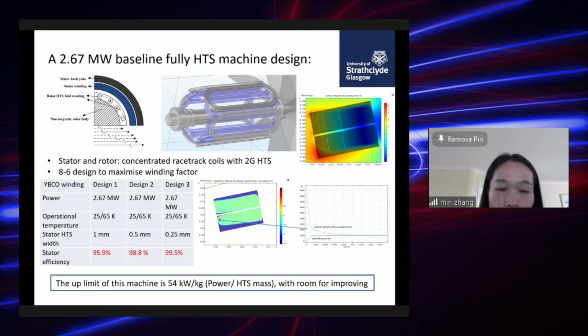In this simulation, we consider 3 different scenarios, with different widths for the HTS stator winding. For example, assuming we are using striated HTS tapes, each striation can be 1 millimeter, 0.5 millimeter, or 0.25 millimeter wide. We then calculate the stator efficiency for all the different designs. We get to the conclusion that if we can reduce the filament size of the HTS winding to below 0.5 millimeter, we can achieve a very good efficiency for the HTS armature winding.